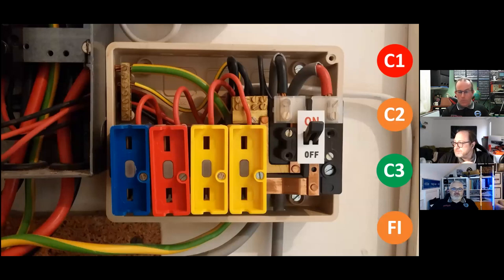Where are the CPCs for all of them? Because there's only one I could see other than the main CPC for the board, and I can only see one CPC connected for all four circuits. I think it goes to that cable coming out to the right. Where are the circuits going anyway? They're going into the enclosure to the left, so the CPC is probably in there with them. Yeah, this is the one to the left. It was one of those three-way split Wylex things with the off-peak and the hot water and the normal circuits all in the same box. Is that where the CPCs were? Probably. Okay. Because they all come from that enclosure there.